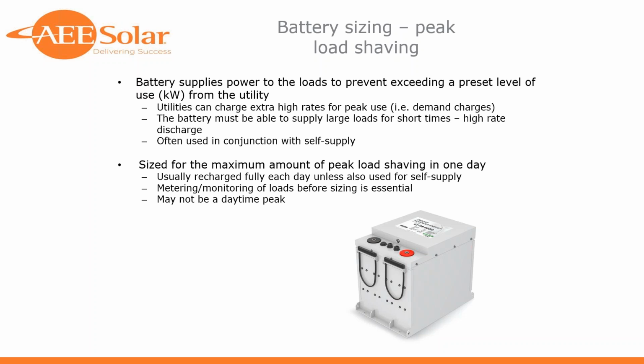So in working with customers on this, we've advised them, when they're doing the metering and gathering all the inputs, to look for loads that have high turn-on current, not being used continuously, but kind of peaky loads that are driving that peak kW number. And as you said there, Brad, knowing that you're probably going to need a battery technology that can support high current discharge, that is not going to have issue with potentially multiple cycles a day, is critical.